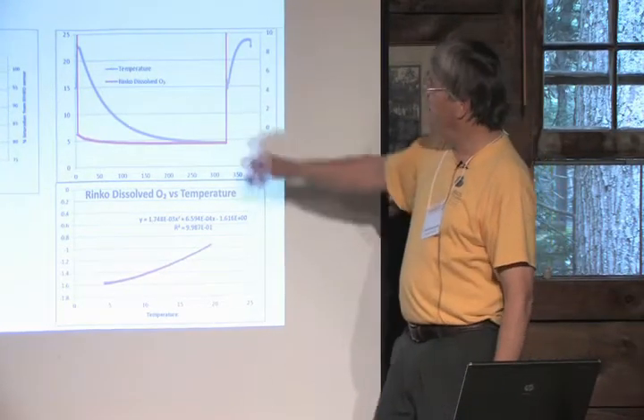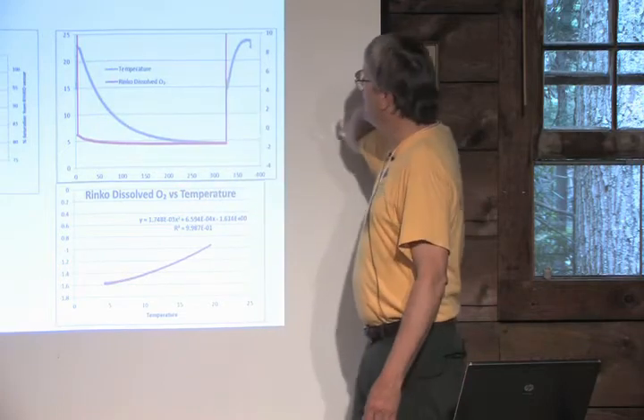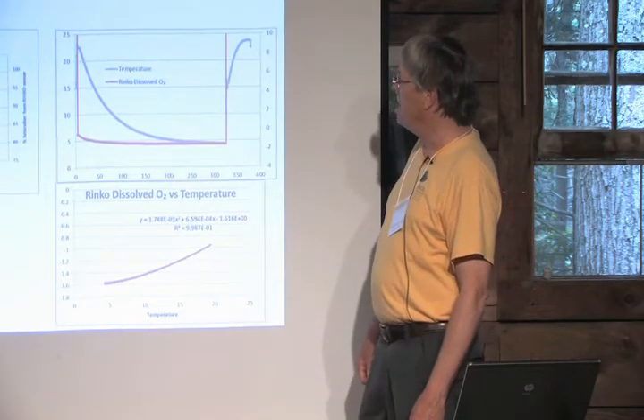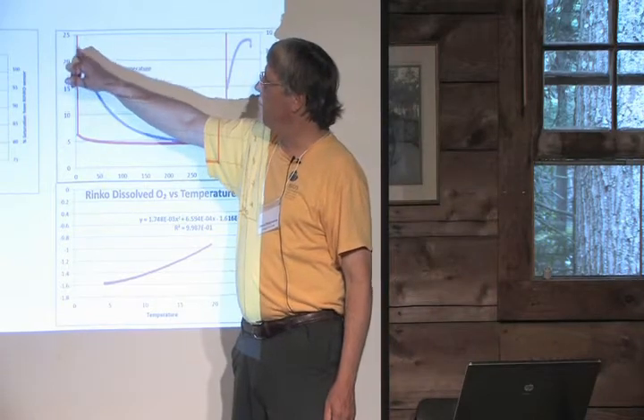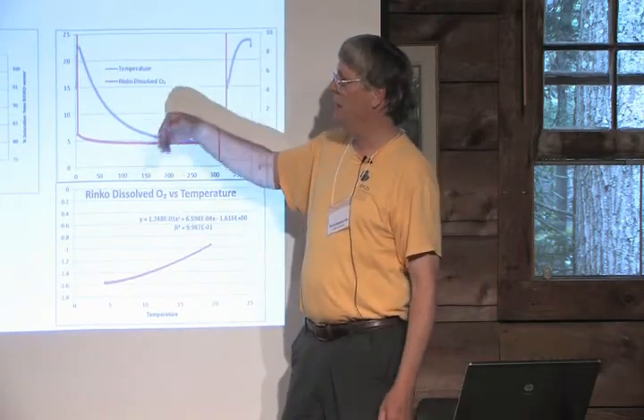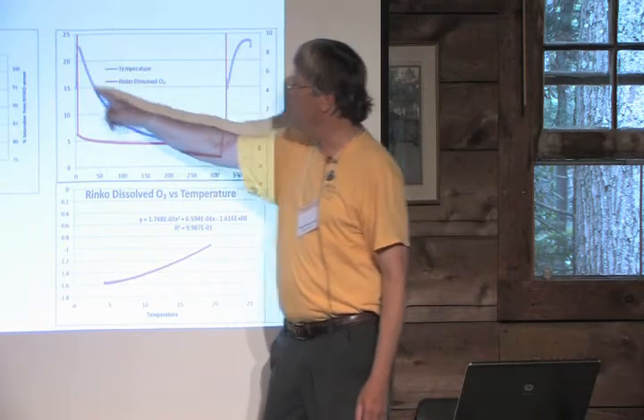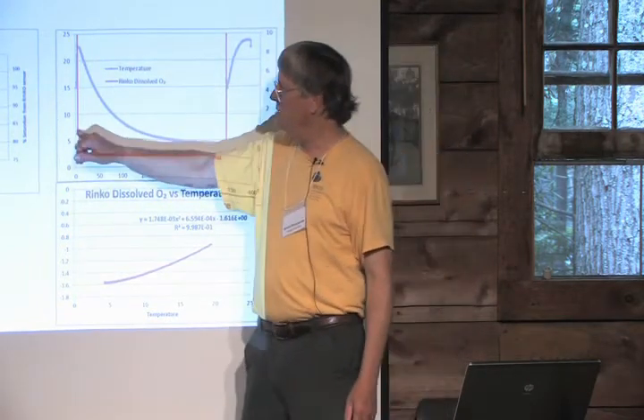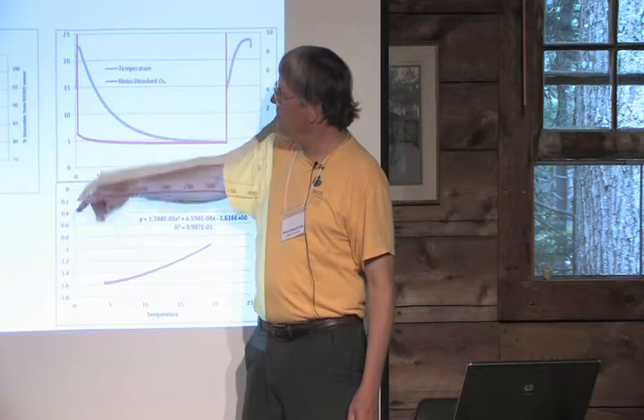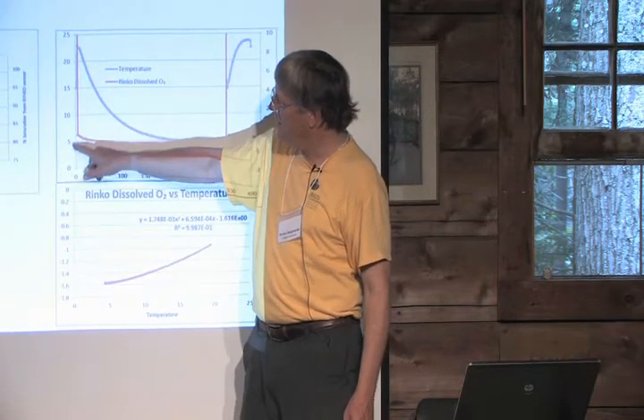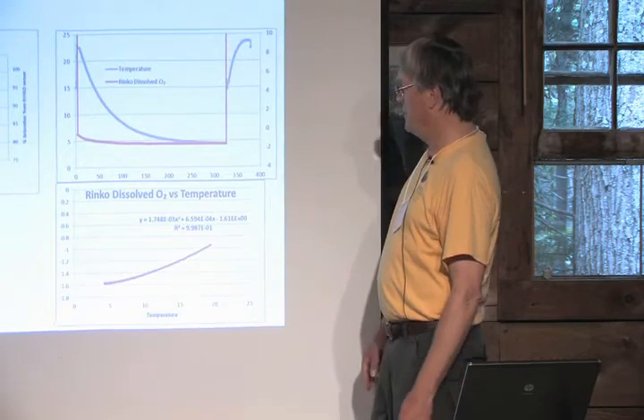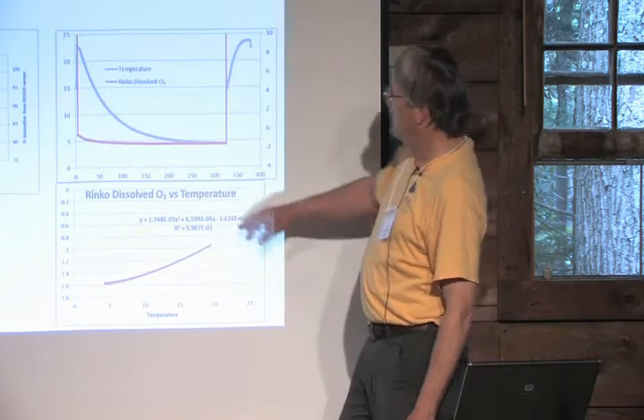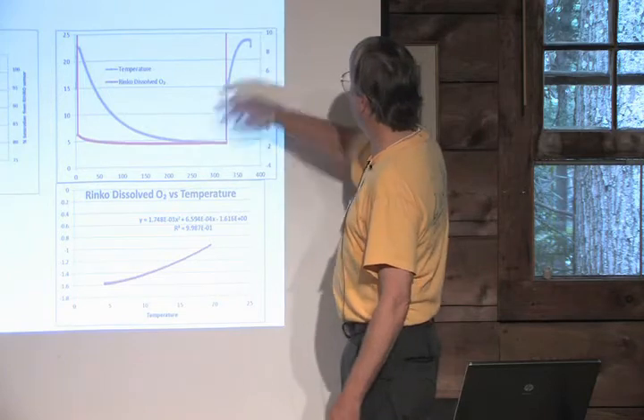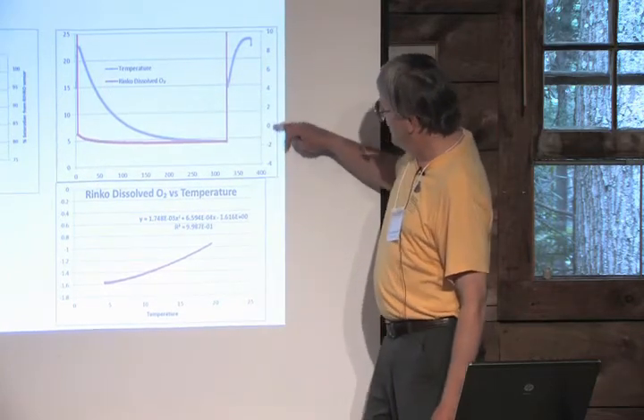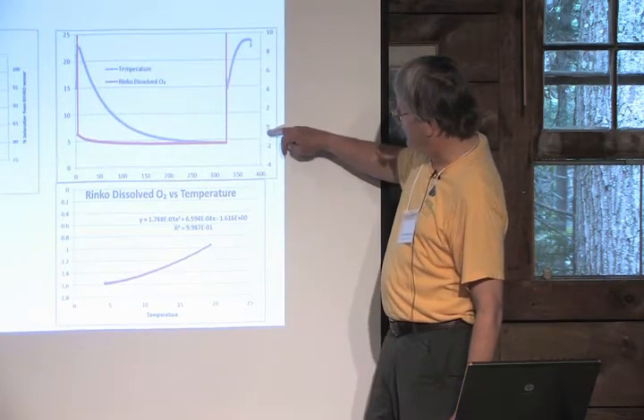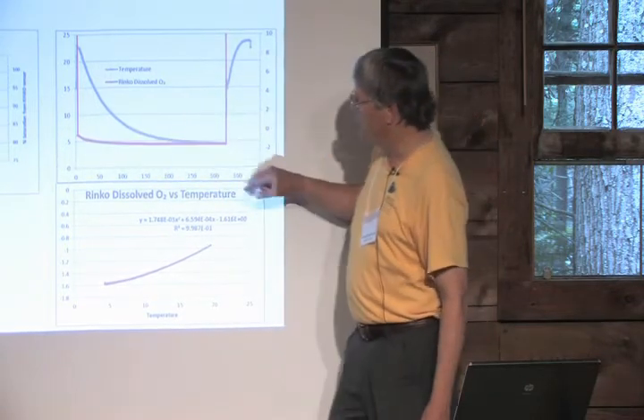Look at the results. Here we put it into a bucket of sodium sulfite, and the temperature was at room temperature. Sodium sulfite had been mixed up at room temperature, and here's the temperature gradually going down as we put it into a cold room, and here's the response. The 0 oxygen, this is a percent of saturation here, and I'm not quite sure why this is. That's temperature. Here's the oxygen over here. The oxygen signal is slightly negative, about minus 1.5%, about minus 1% at warmer temperatures.